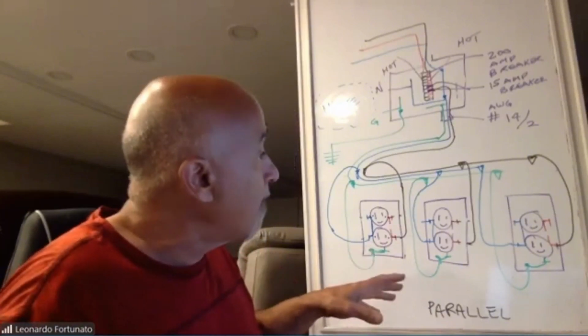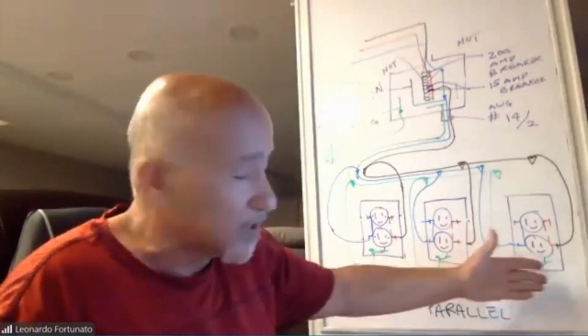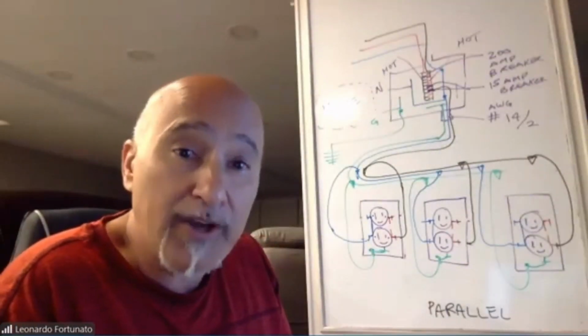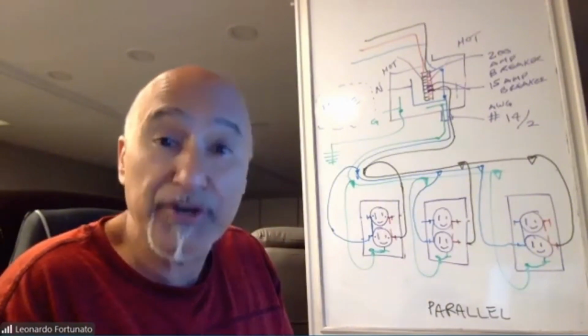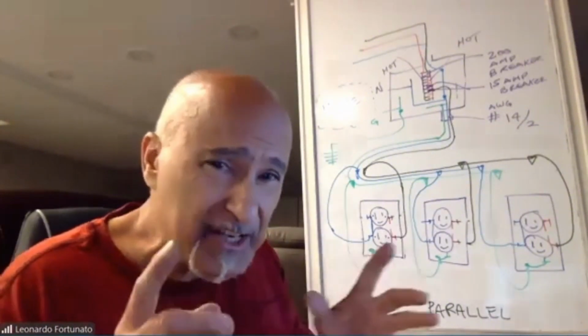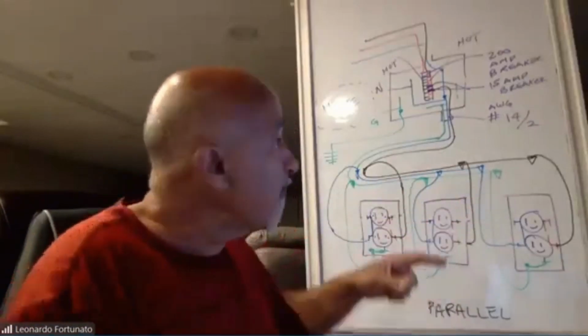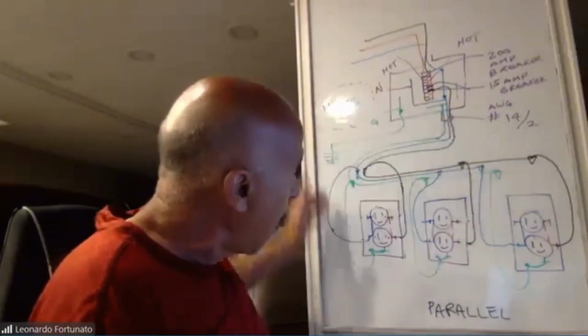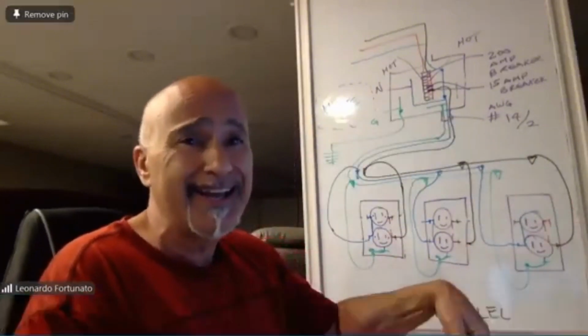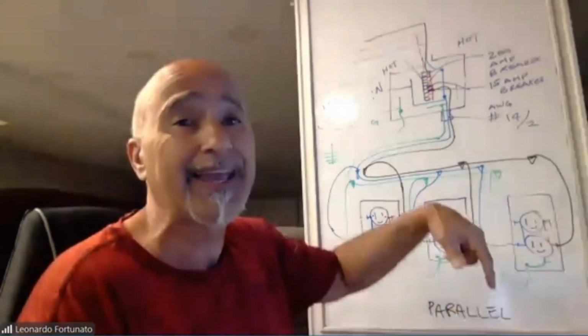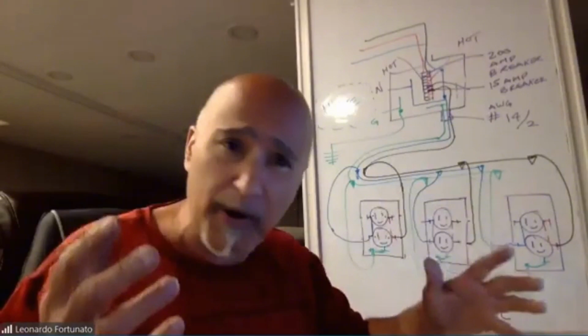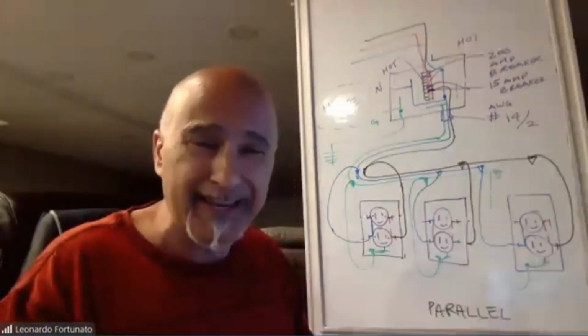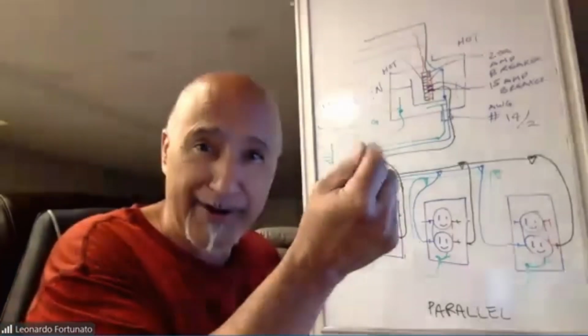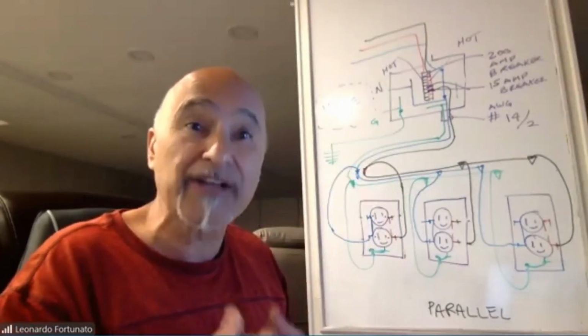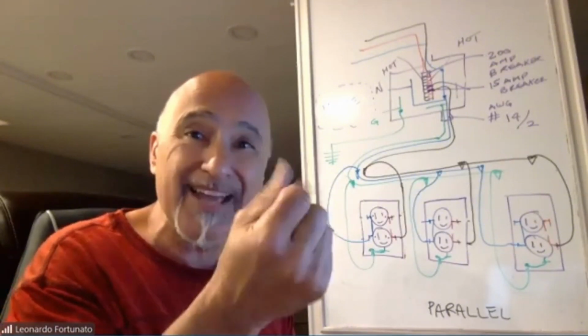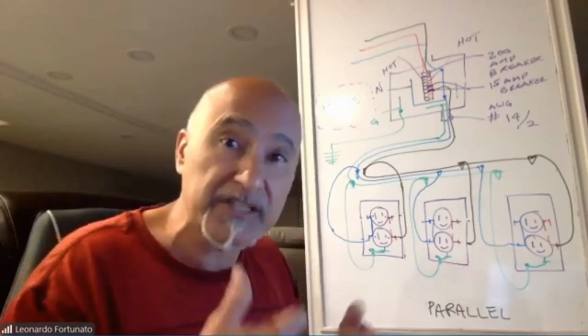So what kind of cable am I going to run from the panel to these receptacles? Am I going to run another 14-2 cable? Yeah, I could run another 14-2 cable. But ladies and gentlemen, we have to be smart here. If I run another 14-2 cable from this breaker all the way to all of these receptacles, remember, we only needed one more conductor, but now I'm bringing a neutral once again, which is perfectly fine. I can do that. But now, number one, I'm wasting money on wire, because I'm running extra wire. I'm wasting money on time because it's going to take more time to run a second wire.